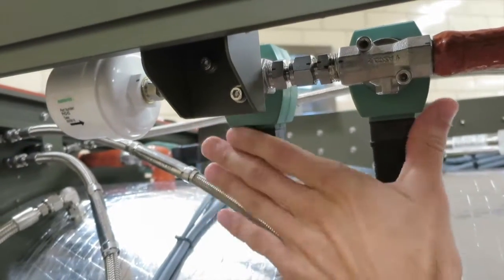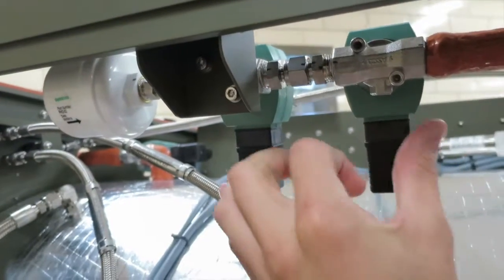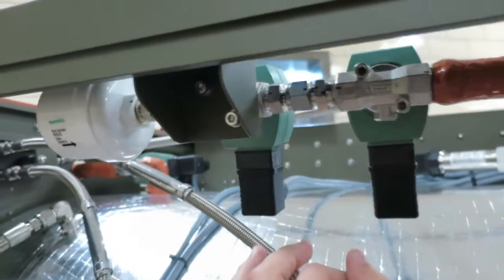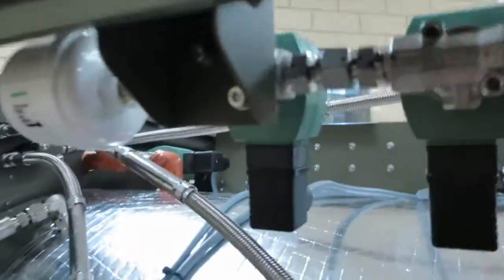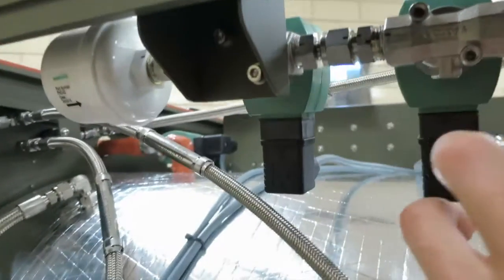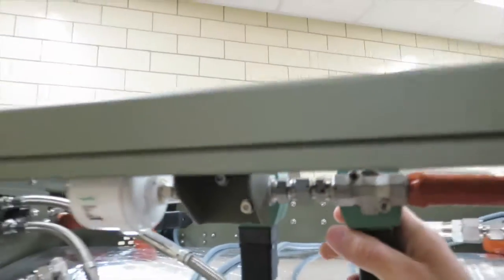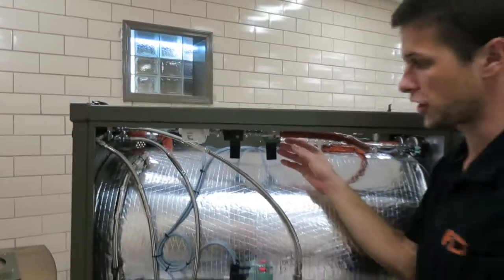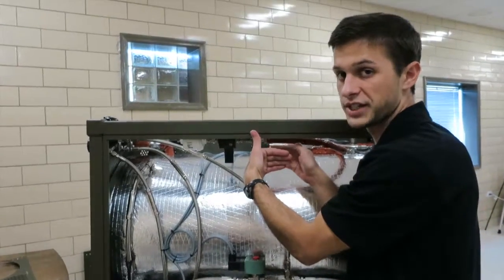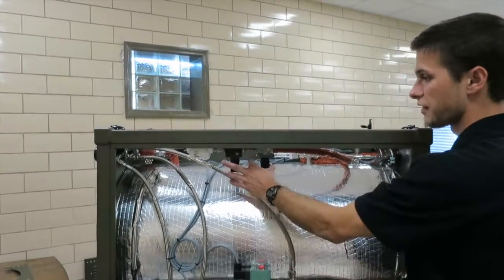So again, these are the vacuum break valves, and very important which direction they go. There's a flow arrow on them, and the arrows should be facing each other. There's also a 1 and 2. So this valve, there's a 1 and 2, and on this valve, there's 1 and 2. So whenever you do maintenance on these, you're going to want to make sure you install them with the flow arrows facing each other. So the vacuum break valves.